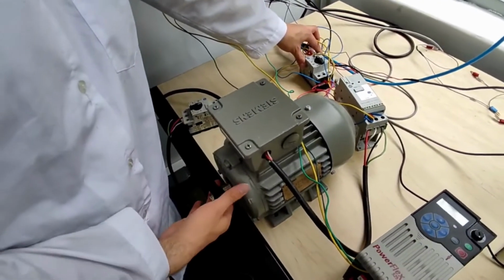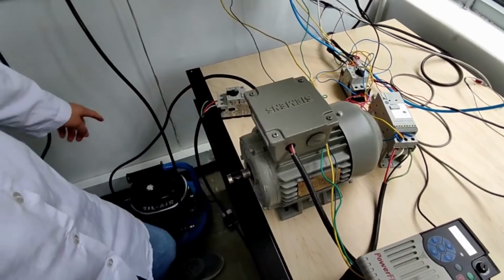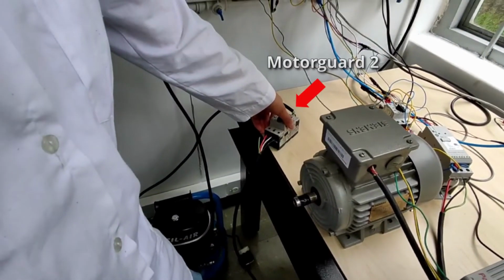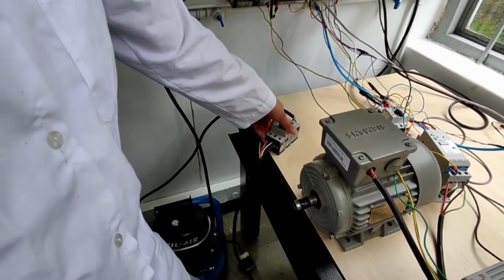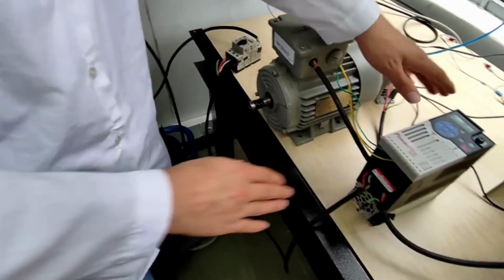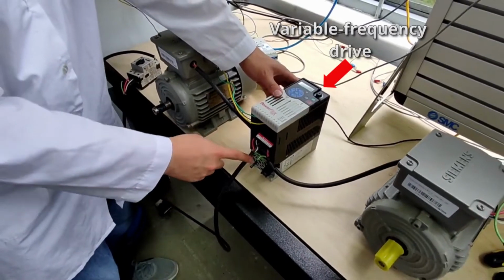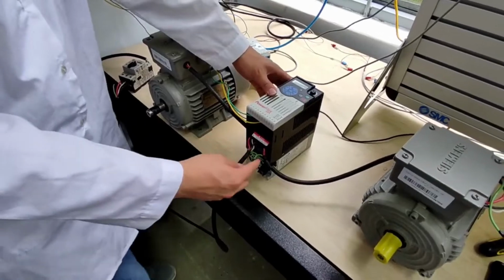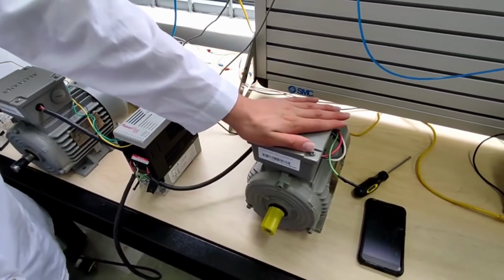The second engine that we can appreciate is a motor that is controlled by the variable frequency drive. This represents the pallet output conveyor. This system starts with the magnetic starter, the variable frequency drive that allows us to control the frequency given to the engine from 0 Hz to 60 Hz. This is possible with the analog output of the PLC from 0 volts to 10 volts.